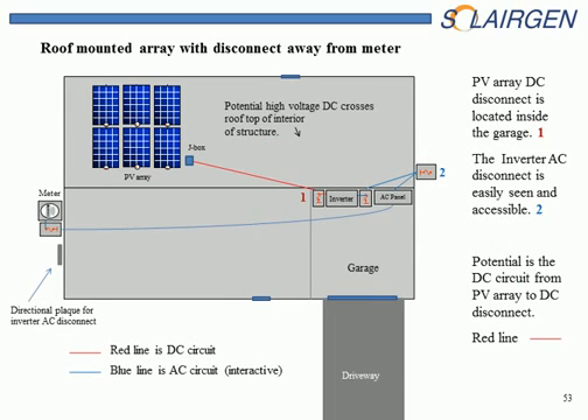Here we have a roof-mounted array with a disconnect away from the meter. So we have the meter on one side of the house and the AC disconnect, where number 2 is located, on the outside of the house, on the opposite side. So we should have a plaque over by the meter indicating where that AC disconnect is, number 2. The DC disconnect may be on the outside of the house, but more than likely they took a straight shot and went to where the inverter was and put the DC disconnect there, because it only has to be readily accessible to meet the NEC code requirement. So the DC disconnect and the inverter will have to be spotted.